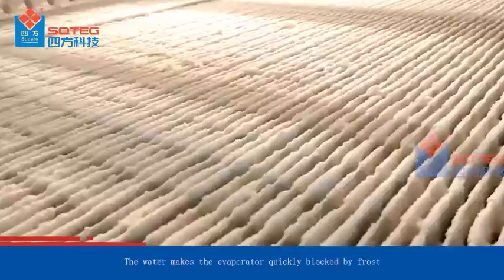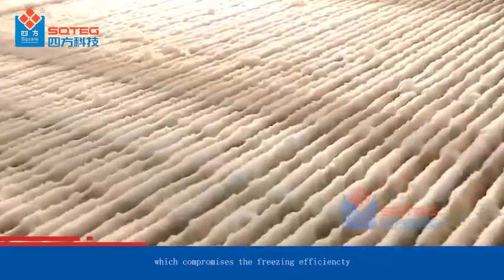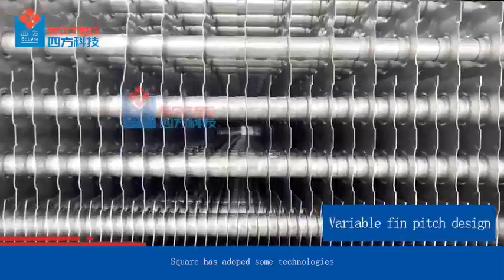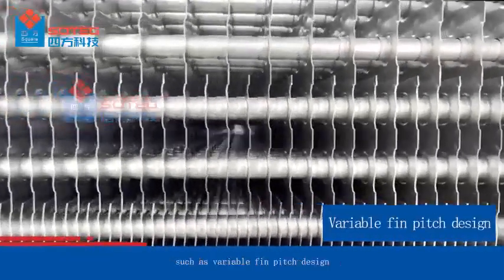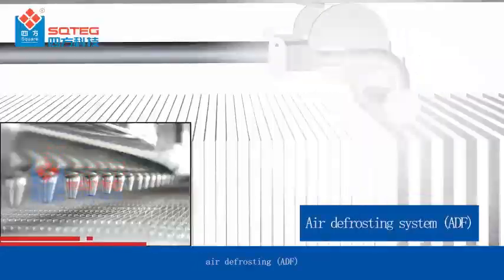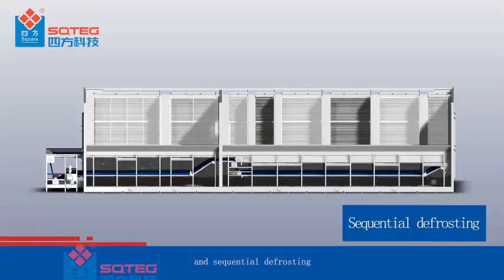IQF freezers typically process large amounts of foods with high water content. The water causes the evaporator to become quickly blocked by frost, which compromises freezing efficiency. To extend continuous production time and improve efficiency, Square has adopted technologies such as variable fin pitch design, air defrosting, and sequential defrosting.